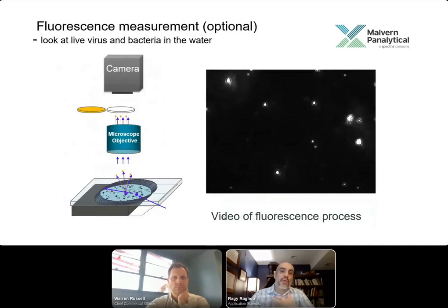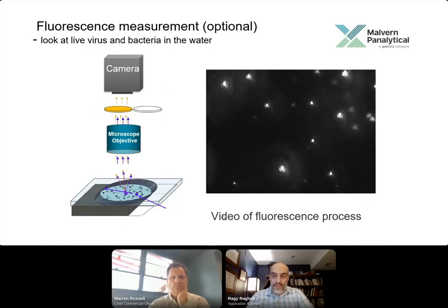And so you can, again, look at fluorescently labeled particles, and that's simply a matter of doing the analysis in what we call scatter mode, and then inserting the corresponding long-pass filter that matches your laser source, and doing the fluorescently labeled measurements.